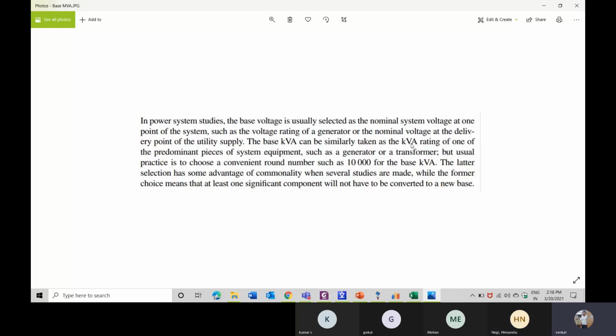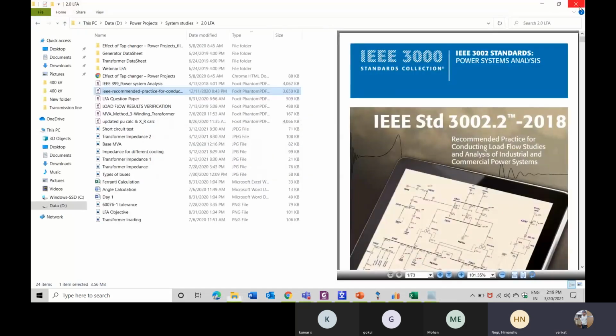The base KVA can similarly be taken as the KVA rating of one of the predominant pieces of system equipment, such as the generator or the transformer. Usual practice is to choose a convenient round number, such as 10,000 for the base KVA. This selection has some advantage when studies are made, since the former choice means at least one significant component won't need to be converted to a new base value. The base MVA should be chosen as, say, the rating of one of your transformers, or you can assume a value like 100, 200, 500, or 1,000.